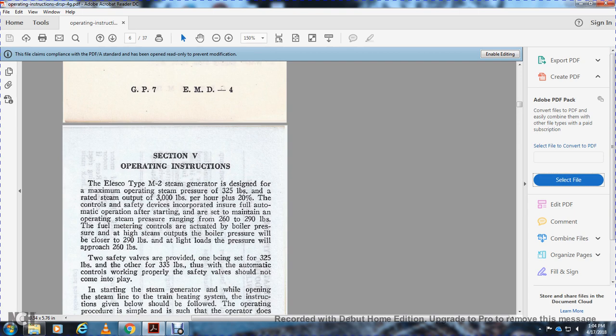Alright, Section 5, Operating Instructions. The Elesco Type M2 steam generator is designed for a maximum operating steam pressure of 325 pounds. The rated steam output is 3,000 pounds per hour plus 20%. The control and safety devices are incorporated to ensure fully automatic operation, starting with a set and maintained operating steam pressure ranging from 260 to 290 pounds.